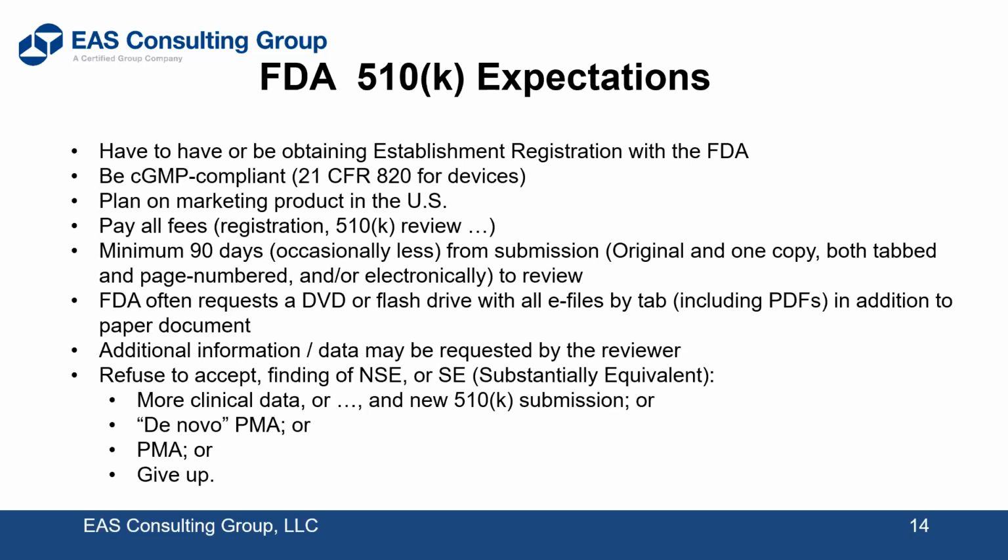Now, the FDA requires 1 hard copy, paper copy in a submission, and 1 electronic copy per a specified format that they outline on their website. And that's usually submitted by an old DVD or more likely a flash drive. During the course of the review, the FDA may call you for additional information. They'll stop the clock while you're trying to get that information submitted back. They may give you a deadline. In most cases they will, maybe 180 days or so, within which you have to get that information back to them. But again, that may tend to drag the review out.